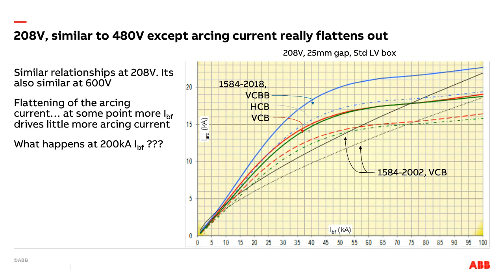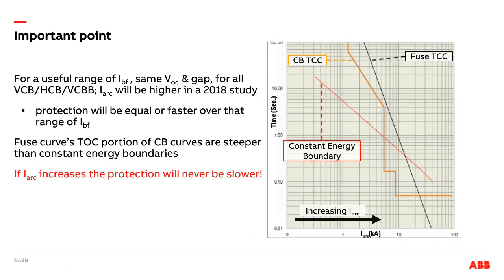And what you see from here is that the values calculated per the new standard are going to be higher than the values calculated per the old standard. So in the paper exercise that is an arc flash study, I am dealing with a different input into my time current curve analysis. So when I look to my time current curves, again, it doesn't matter if it's a fuse or a circuit breaker, the issue is if my current is higher, notice the direction of this arrow, I am going to interrupt this curve further to the right.